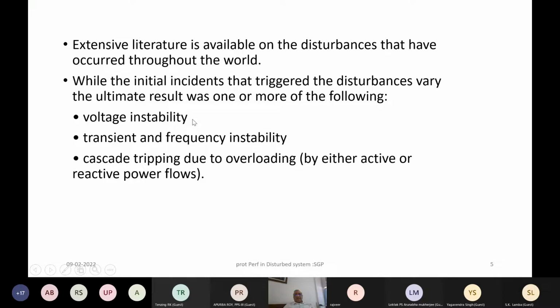Voltage instability related protection aspect which was encountered during the 2012 grid collapse was basically the load encroachment phenomena and operation of zone 3 due to overloading of the lines. Transient and frequency instability resulted in tripping of lines on power swing, and also tripping of generators due to under frequency conditions. So both these are very relevant. And then there was, of course, cascade tripping of lines due to successive overloading one after another. Also, the reactive power flows resulted in excessive voltage drop at the receiving end of the transmission lines.